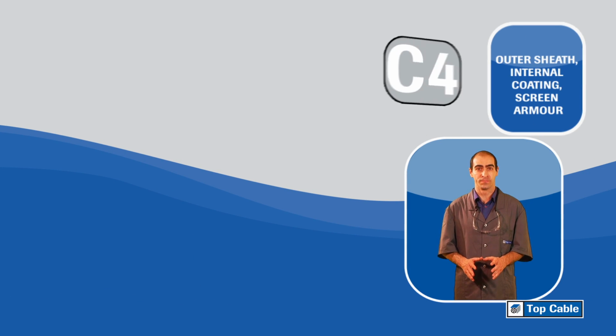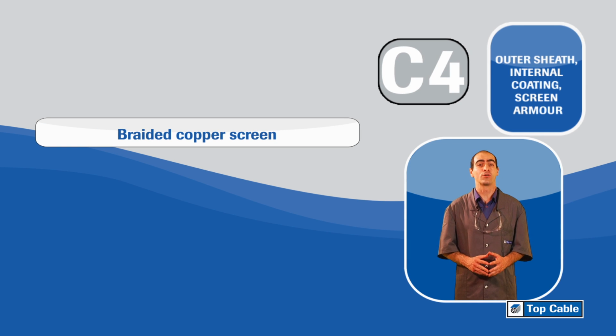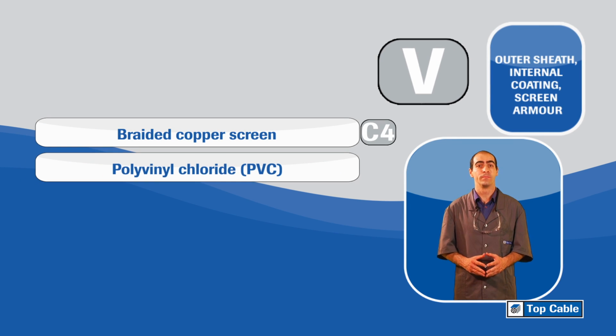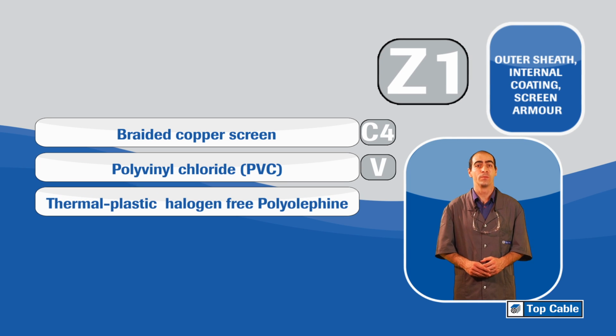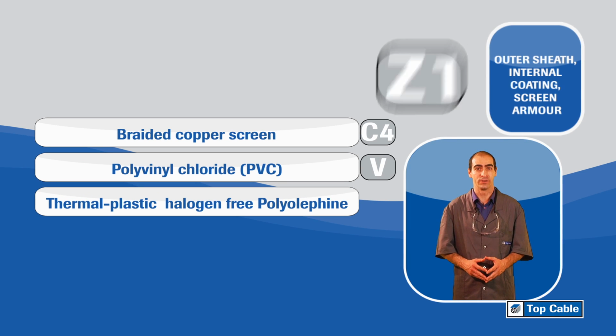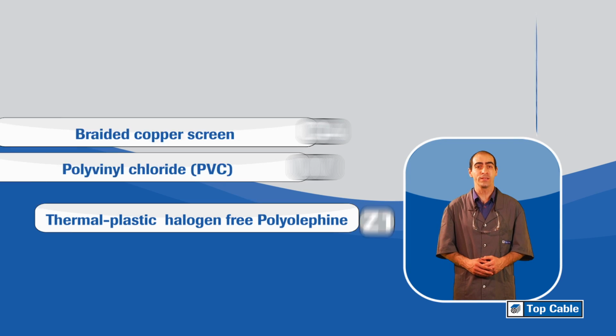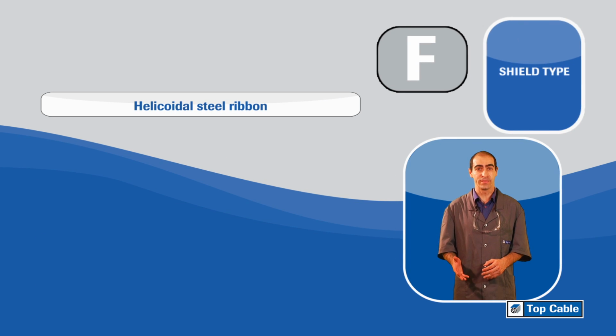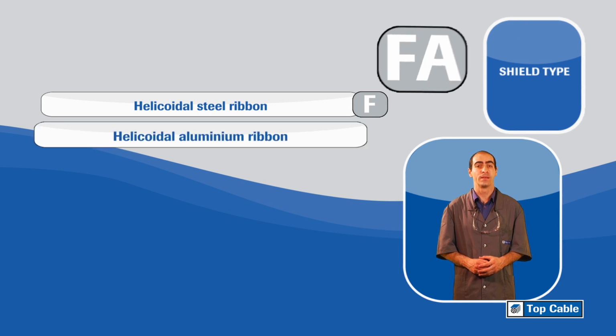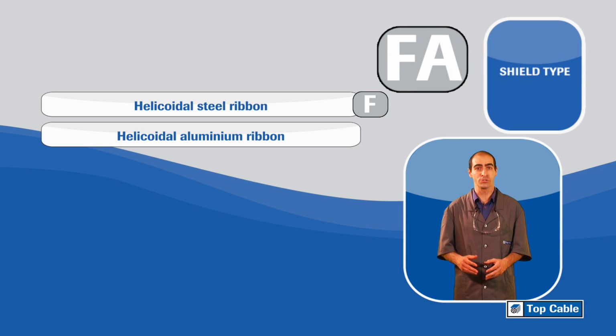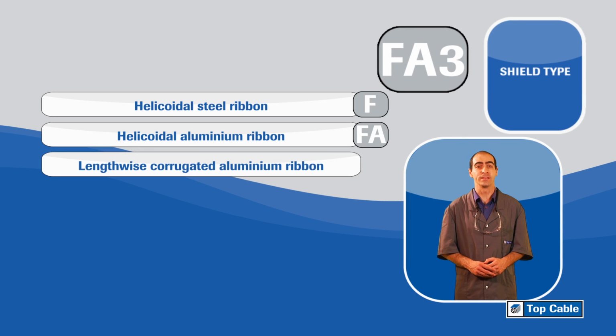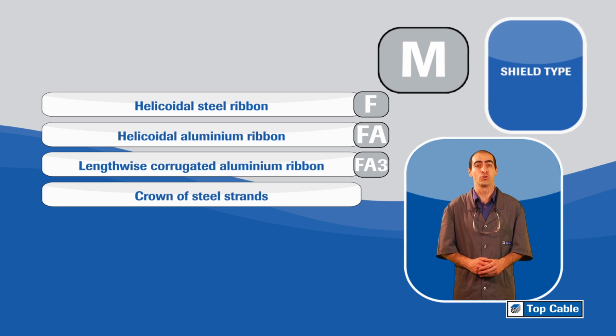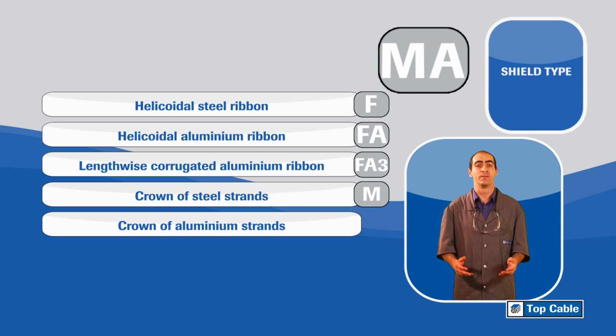The most common screens, internal coatings and screen armors are C4, braided copper screen, V, polyvinyl chloride, PVC, Z1, thermoplastic halogen-free polyolefin. The most common armors are F, helicoidal steel ribbon, FA, helicoidal aluminium ribbon, FA3, lengthwise corrugated aluminium ribbon, M, crown of steel strands, MA, crown of aluminium strands.